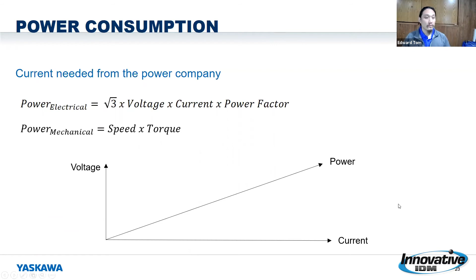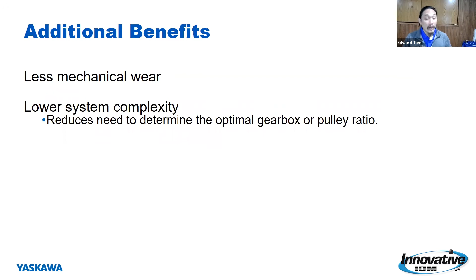Now, that's looking at what we gain from a power standpoint. Some additional things I mentioned: you have less mechanical wear when you jump over to using a VFD. Your system complexity certainly goes down. The reason is that instead of having all the gearboxes, pulleys, and all that, you may now just have a drive and a motor directly connected to your load. Now, you may find you need a gearbox for various reasons, but it will depend on the system that you have. And the regulation is going to be a lot tighter. You have a wider range of regulation, but also a tighter regulation because we have fine control of that motor. So that's the basics of how a motor operates, the basics of a VFD, and also the benefits you would get from using a VFD.